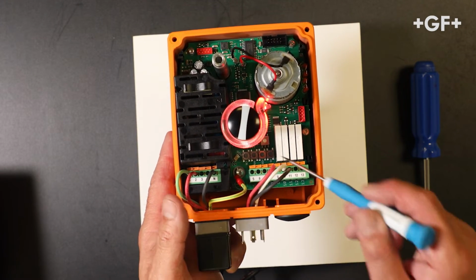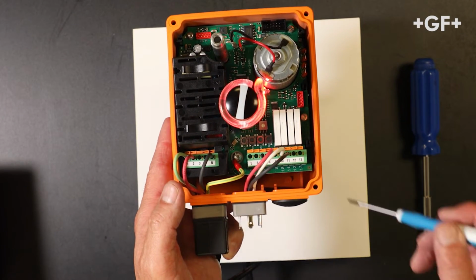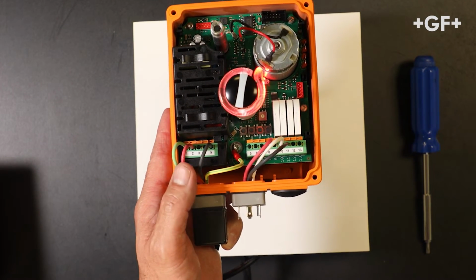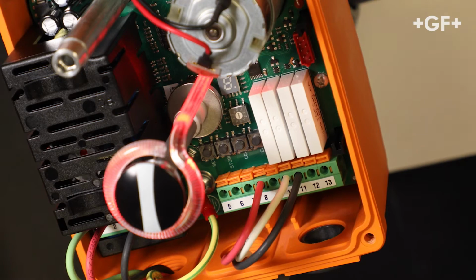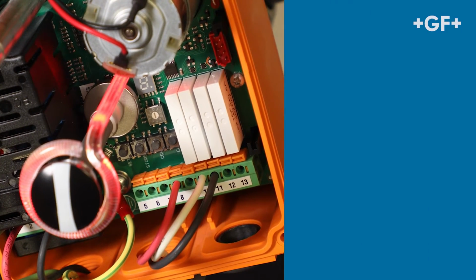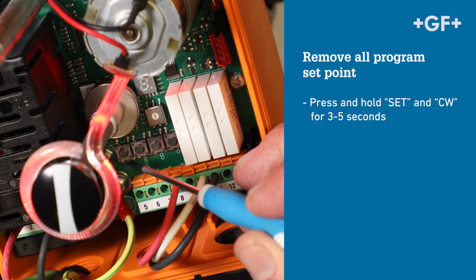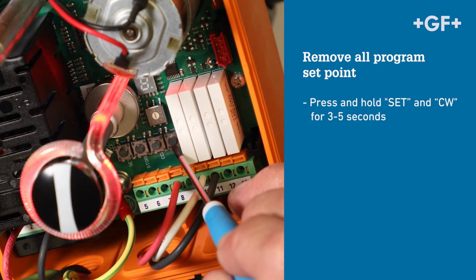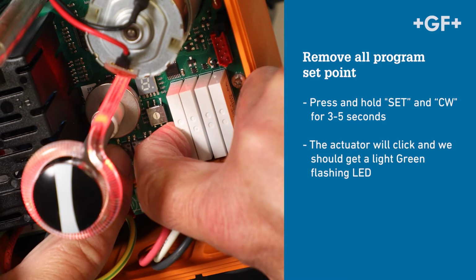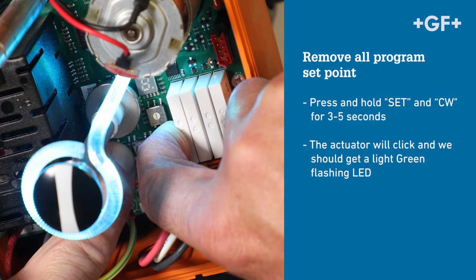Also, programming the actuator is a timed function. The unit will time out after 10 seconds of no activity. First, remove all programmed set points. To do this, press and hold Set and CW for 3 to 5 seconds. The actuator will click, and we should get a light green flashing LED.